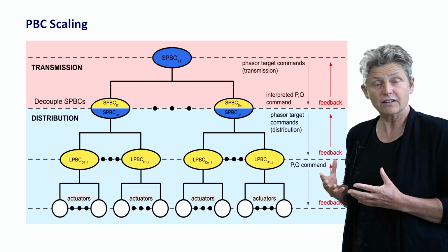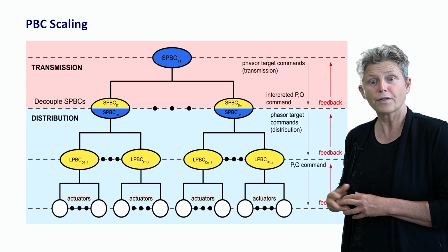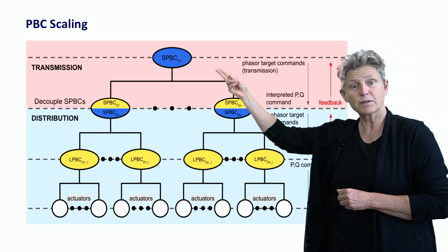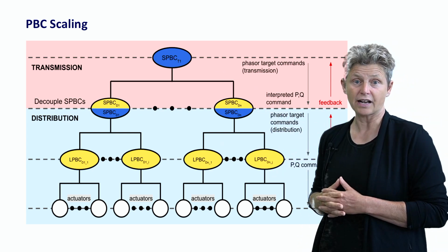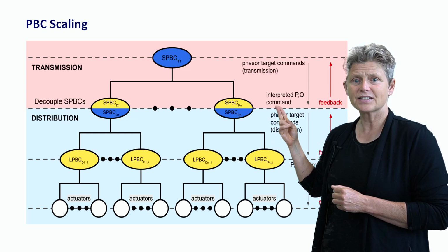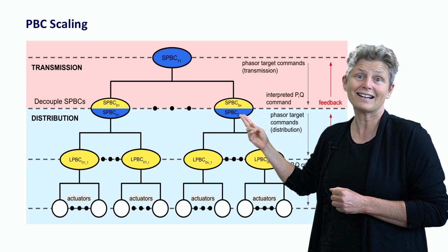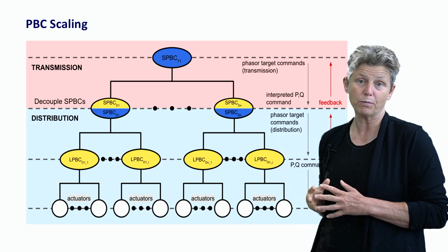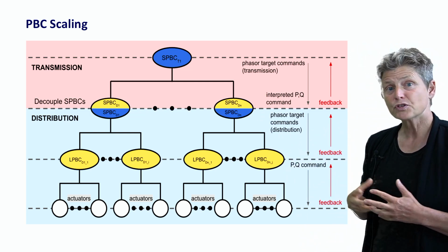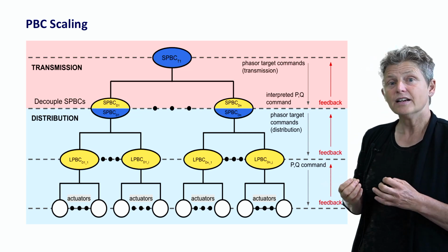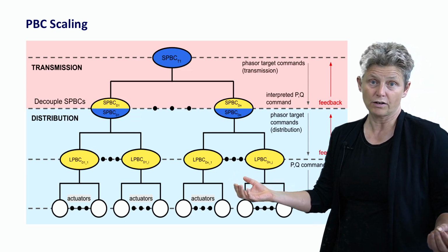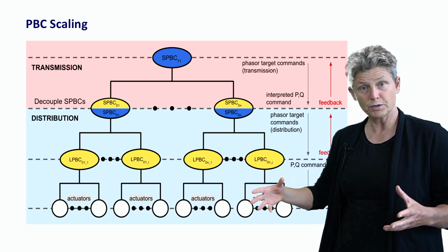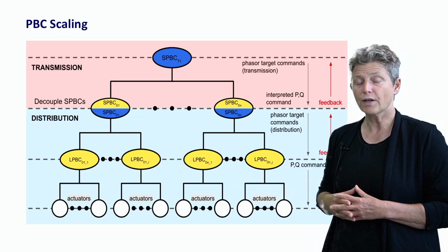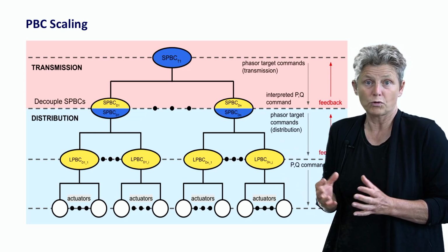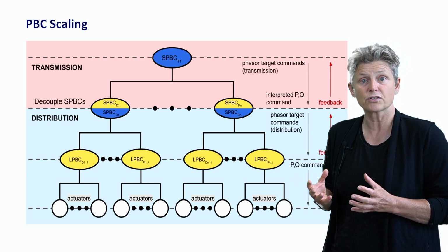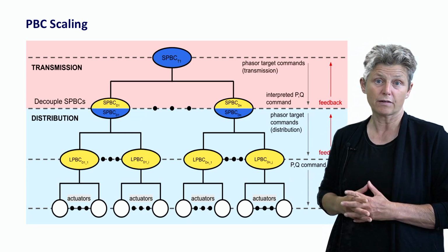This paradigm can be scaled up almost in a fractal way, with multiple levels of supervisory control at the transmission scale. In a sense, this controller acts as a local controller facing upward into the transmission network. So you could ultimately specify a designed phasor for every node in a large network, and distribute the control responsibility so that local groups of controllers and resources each have a zone they're responsible for.